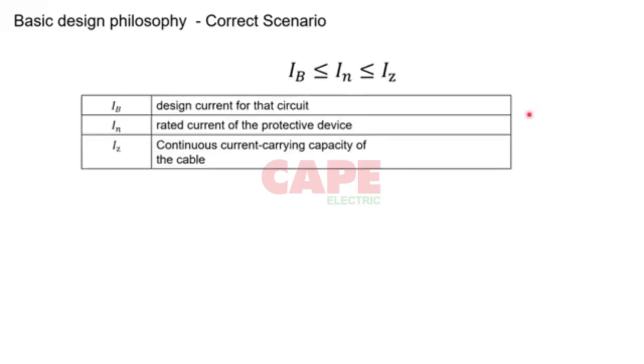Now I will show you a basic design philosophy. This expression is there in IS 732, clause 4.4.4.1, which talks about overload protection. There is one more expression below this, which talks about how the protective device needs to be sized for the overload current for MCBs. You can go to this clause and see it, but I'm not going to take on overload today, because that is not what today's webinar is about. In this expression, IB means the design current for that circuit, IN means the rated current of the protective device, and IZ means the continuous current carrying capacity of the cable.